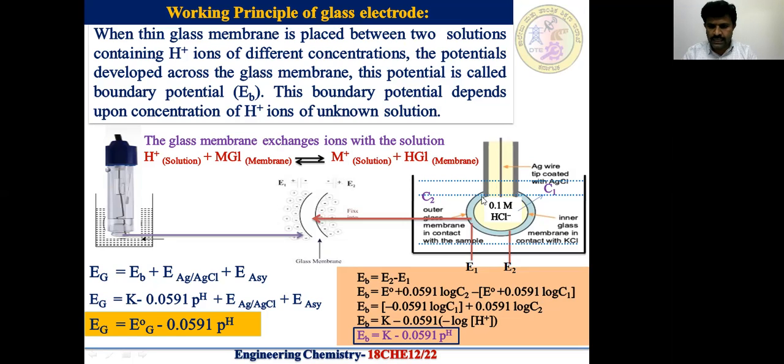I'll repeat the working principle. Assume a very thin glass membrane, which consists of two boundaries. The inner membrane surface is in contact with the internal solution, and the outer membrane surface is in contact with the external solution.